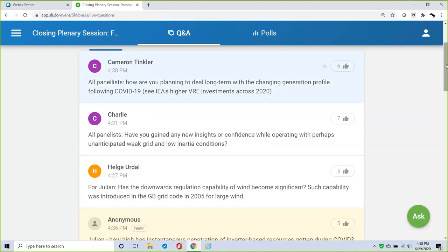Sure, this goes to the heart of our zero carbon operation by 2025, a program we've been working on for about 3 years. That's the grid system operation, the real-time operational part. But in the longer term planning, we're moving to more probabilistic assessments to drive network investment, away from a deterministic security and quality of supply standard. So it affects everything from 10, 15 years out - planning which new investment we need on the grid system - right through to the real-time operation, ensuring you've got enough grid system inertia and short circuit infeed for a safe and secure system. So it really has impacted every corner of our business as to how we operate the system.